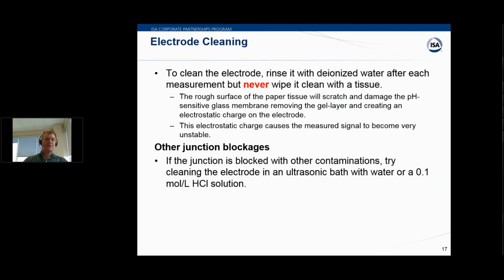And of course, we have to clean things. Everybody thinks, oh, it's just a tissue or a Kim wipe. Generally, even though we think that's really soft, paper tissue can damage the glass. Some of these glasses are quite sensitive. As a minimum, it will remove that gel layer, so it will take some time to reestablish that layer, and potentially you can get static, and that can cause a surge. When you get a static charge, we've all felt the shock.